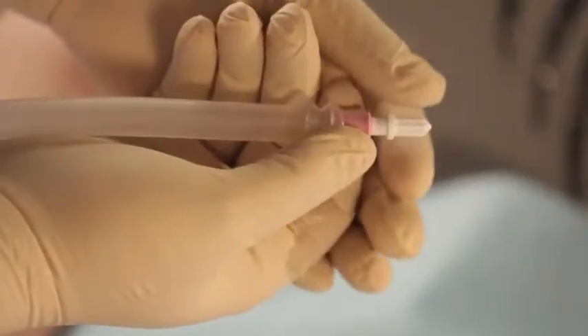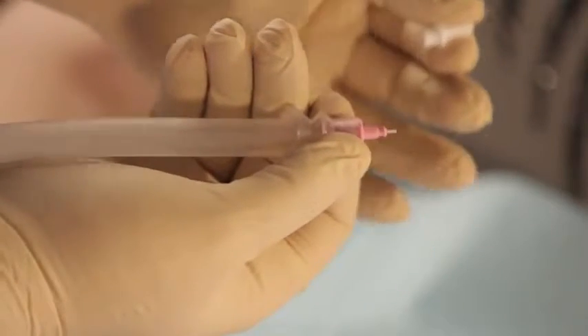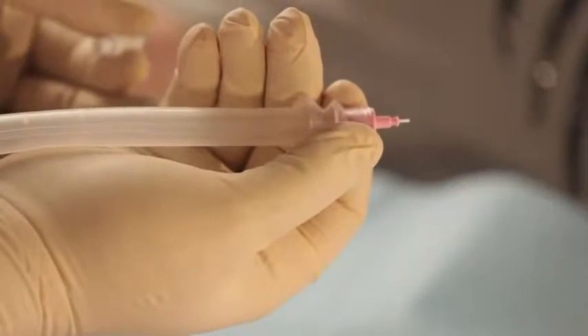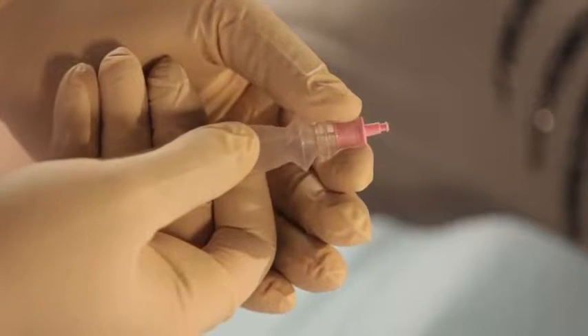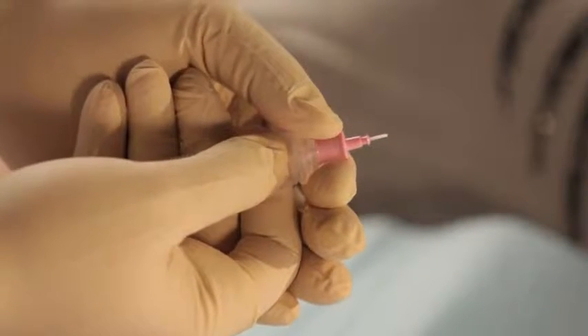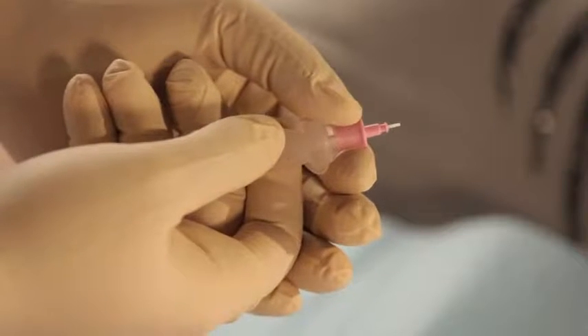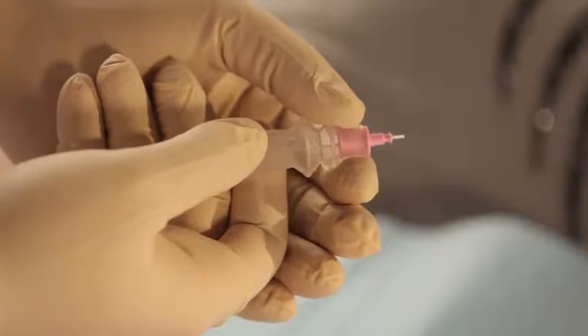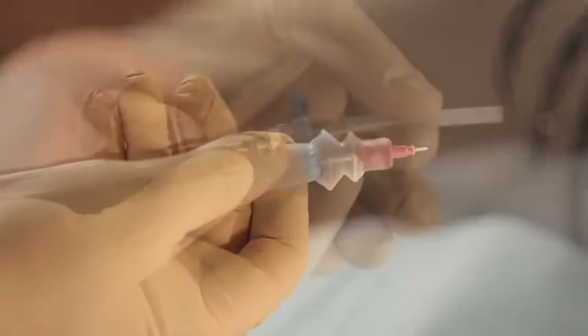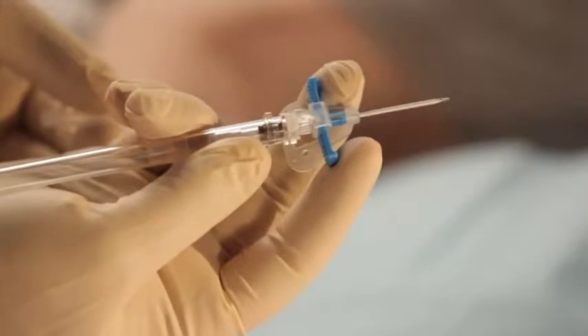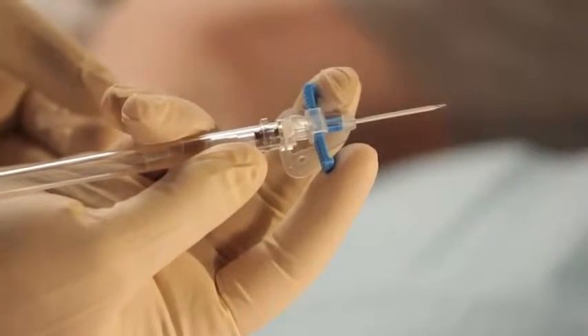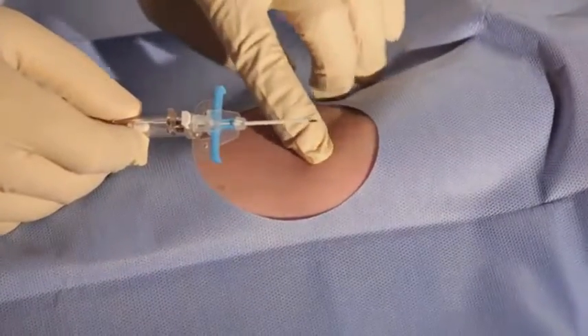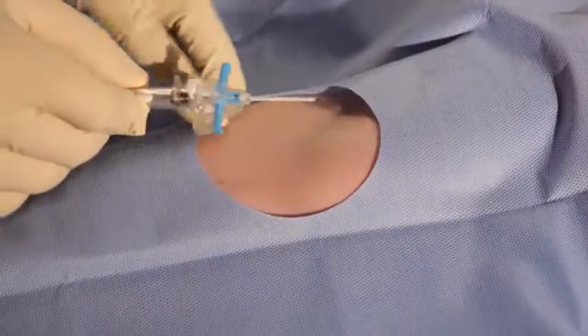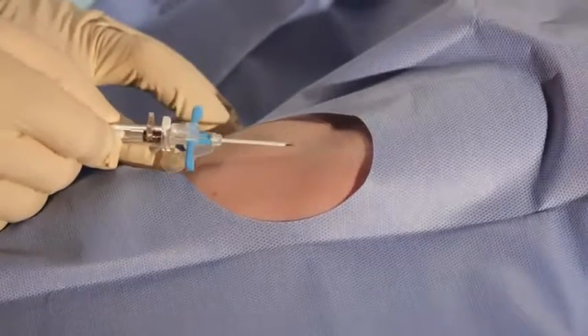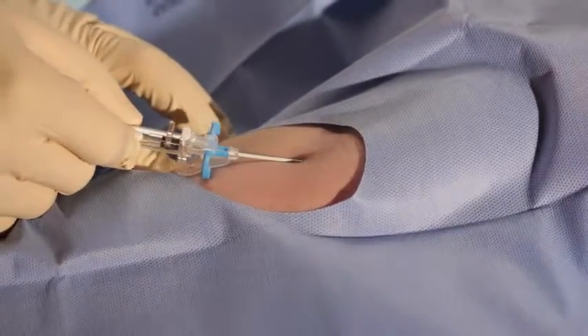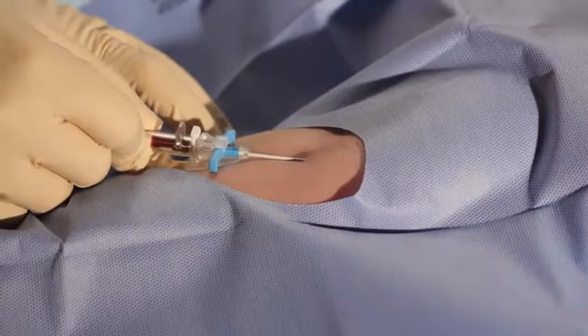Remove cap from catheter sheath and assure that the tip of the M29 is visible. If necessary, advance the M29 slightly by pinching the catheter behind the bellows and pushing forward until the tip is visible. Remove the needle guard and make sure that the needle tip is fully visible. Perform venipuncture, observing for blood return. When seen, lower the angle of the introducer slightly and advance catheter into the vessel.